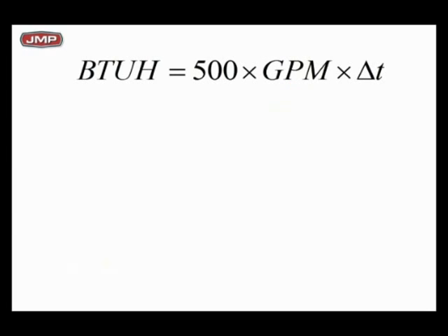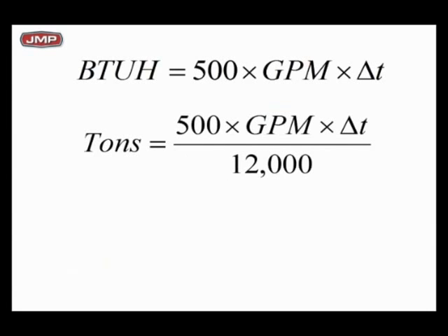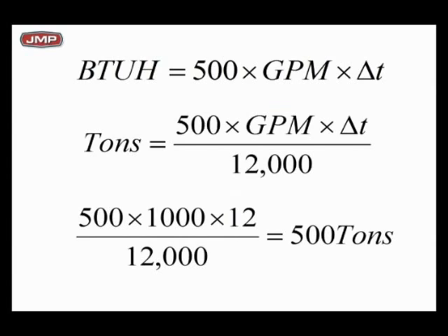So we go back to this formula, and I said 2 GPM per ton is 12 degrees. Now if I look at my chillers and I put my GPM in, a ton being 12,000 BTUs, and if I had a 500 ton chiller at 12 degree delta T, my flow rate's 1,000 GPM. So I like looking at this, because 12 degree delta T on chill water is a good design. Nothing wrong with it. It's 2 GPM per ton. It's a great design. And it makes the numbers simple for what we're doing. But all we're going to do is take that formula and change the delta T.